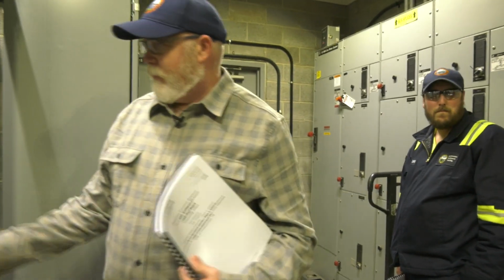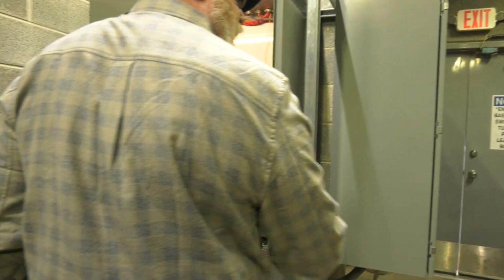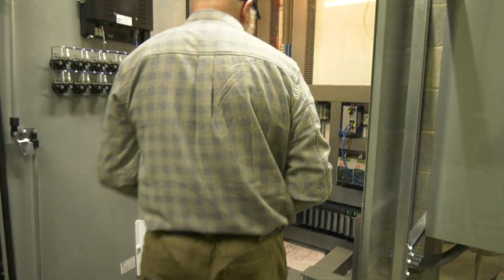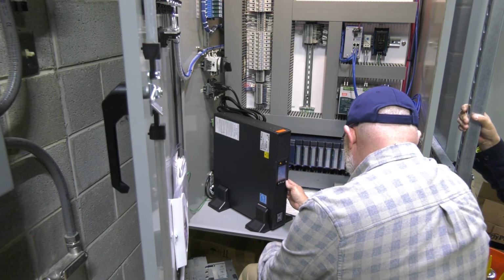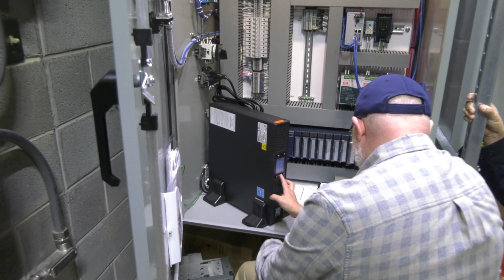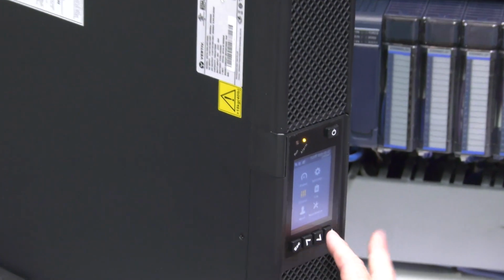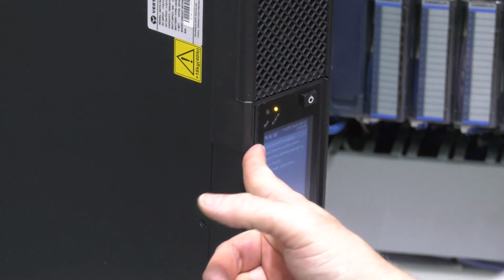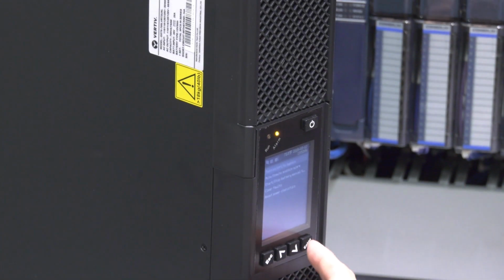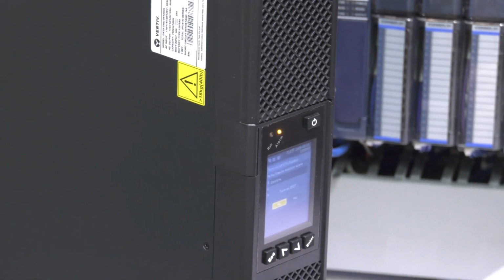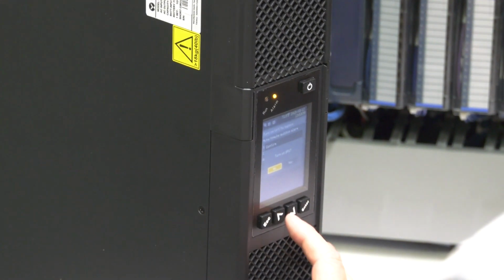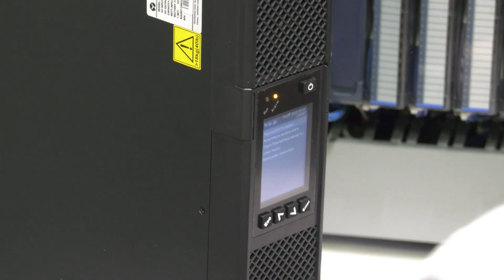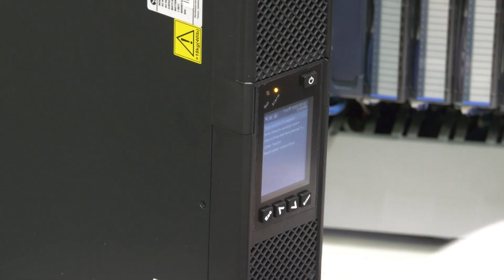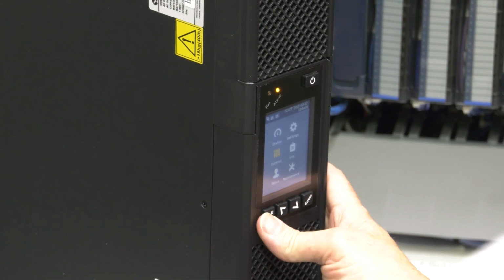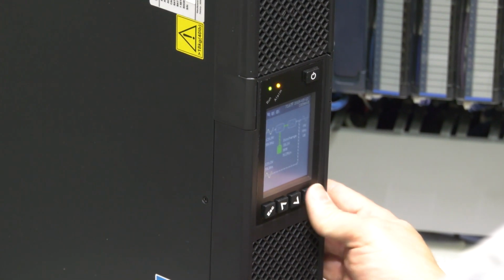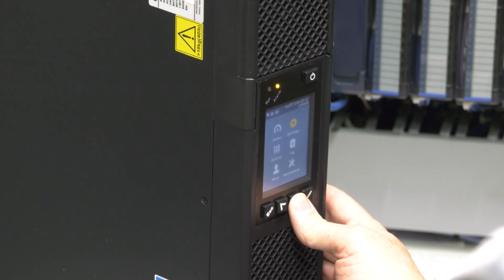Let's go through killing the power and bringing it back up. If you ever have problems, you hit enter, and you can arrow over to control, press enter, and the top one, turn on, off, or bypass, press enter. Enter, and it'll pop up, turn on UPS, yes, and you hear the contactor in there pulling in. Let's see the status.